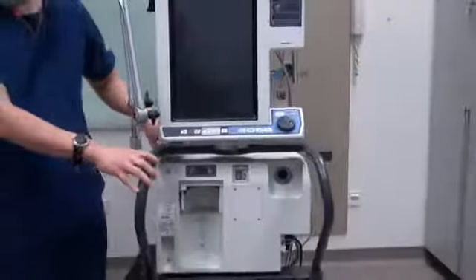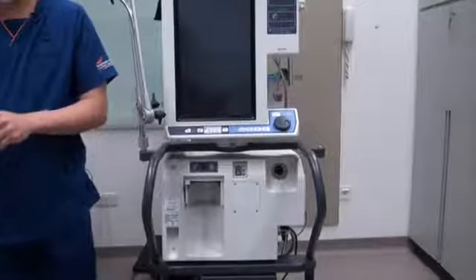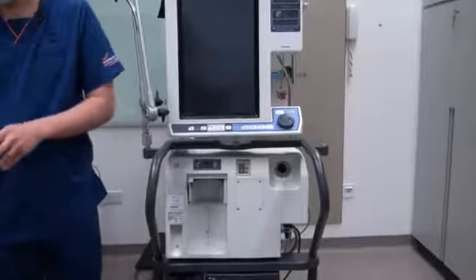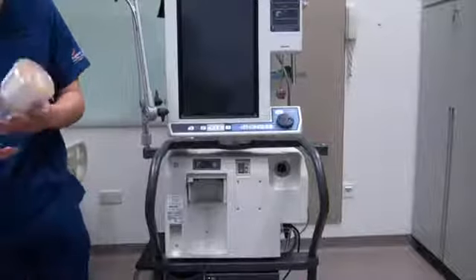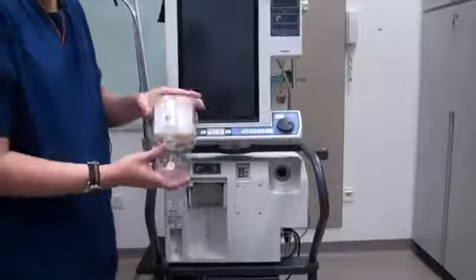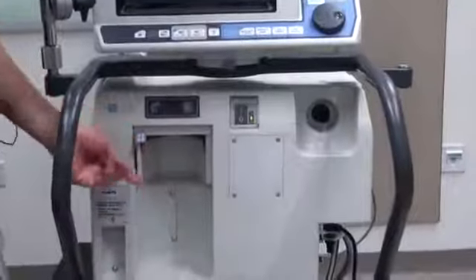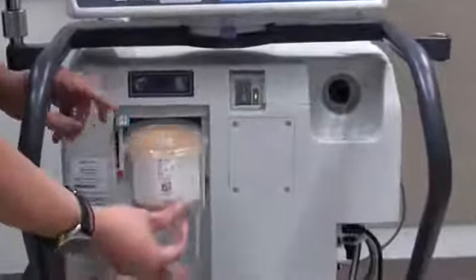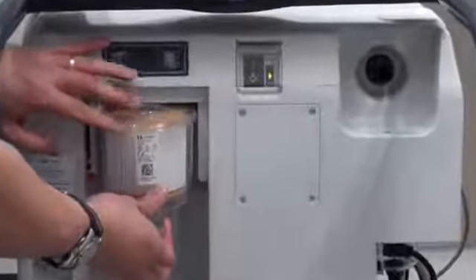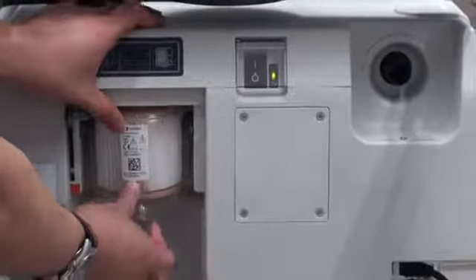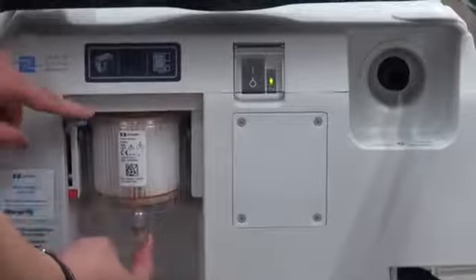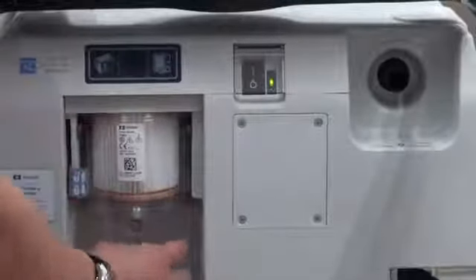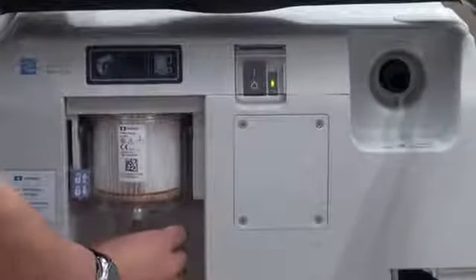All right. And I will now demonstrate how to put in the different components onto the ventilator. The first is the expiratory filter. There is a lever at the side. First of all, you need to lift this up, align the filter in so that it fits smartly into the container, and then push the lever down and make sure that the filter is secure.